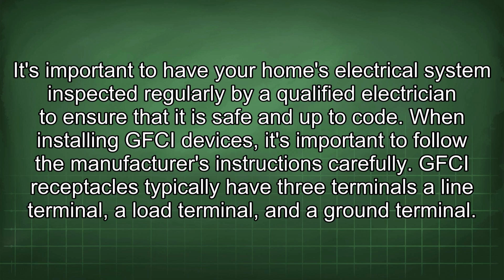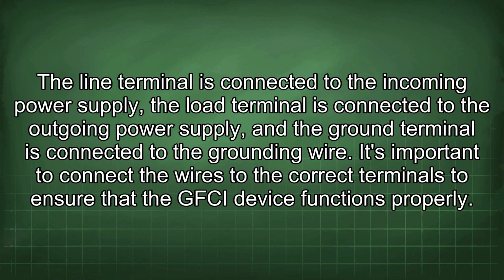When installing GFCI devices, it's important to follow the manufacturer's instructions carefully. GFCI receptacles typically have 3 terminals: a line terminal, a load terminal, and a ground terminal. The line terminal is connected to the incoming power supply, the load terminal is connected to the outgoing power supply, and the ground terminal is connected to the grounding wire. It's important to connect the wires to the correct terminals to ensure that the GFCI device functions properly.